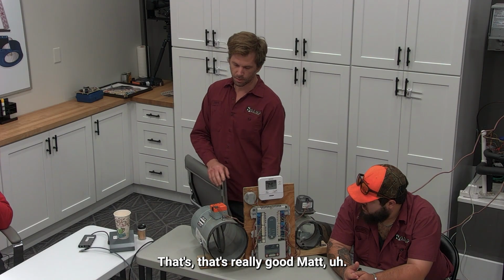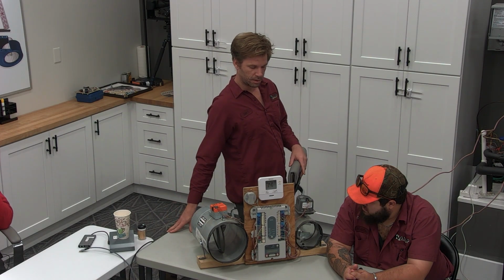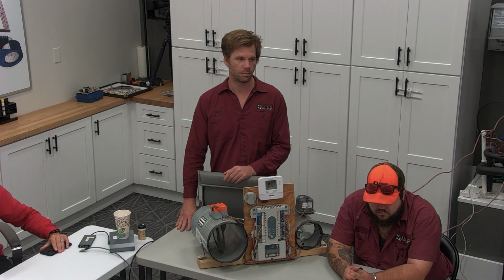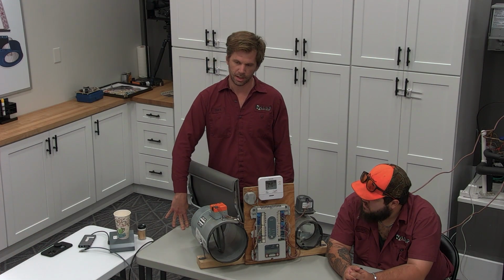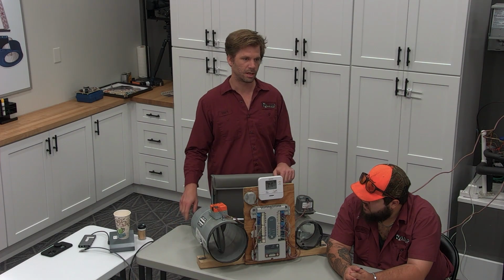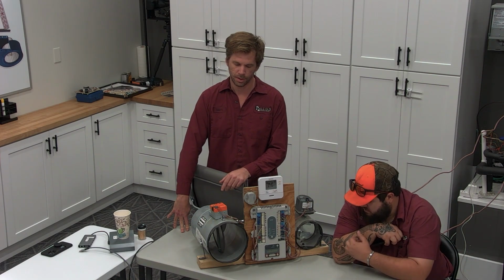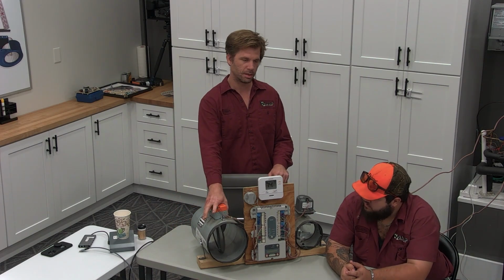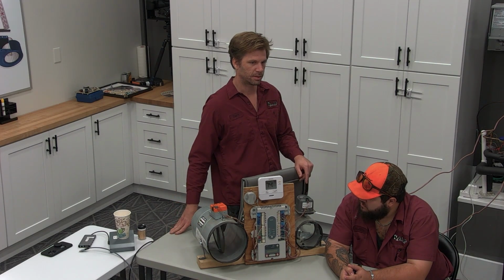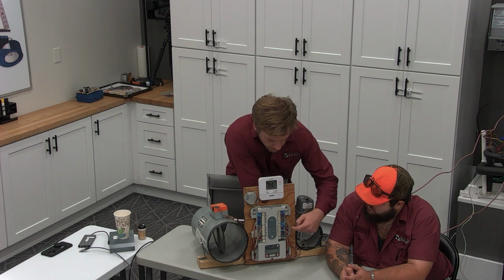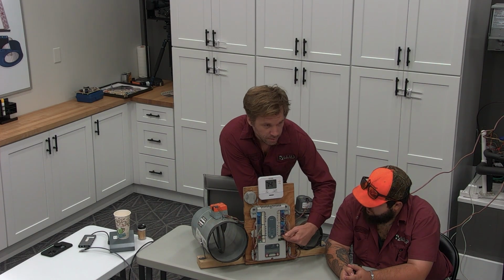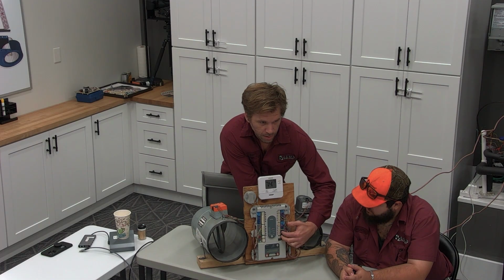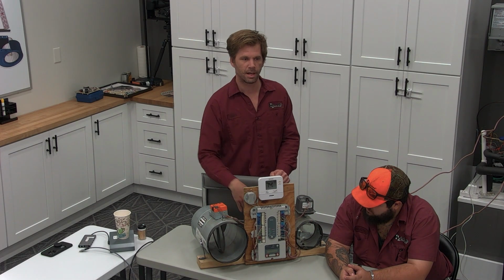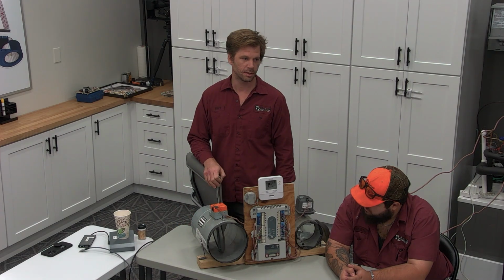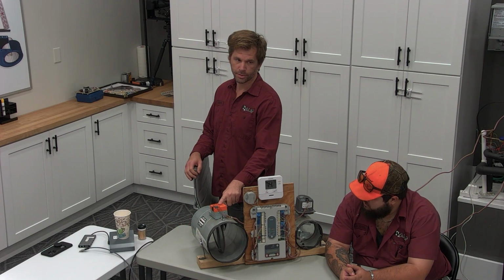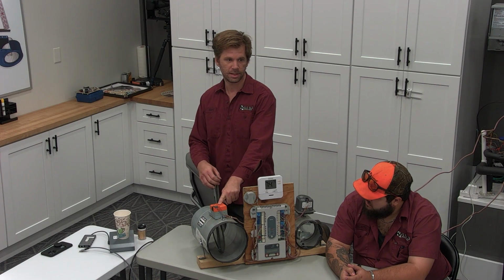That's really good, Matt. And when you are quoting the motors, you need to know the style of motor and communicate that clearly, right? We talked about that last time, but the larger shaft, smaller shaft, Honeywell versus Universal. And Universal can be installed anywhere as long as the damper matches. Like this panel's a Honeywell, so it's designed to fit this, but you also have the closed and open both energized from this panel. Last but not least, if you guys work on Infinity damper systems, the motors are controlled 24 volts open and closed, the same as this setup.